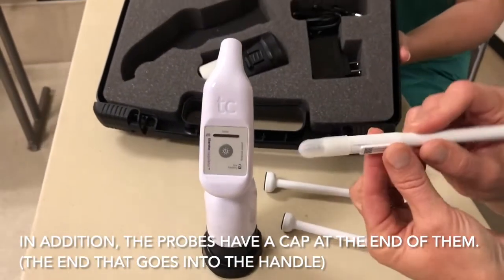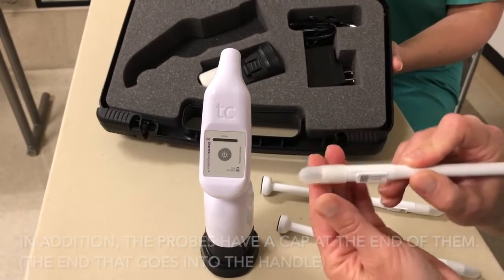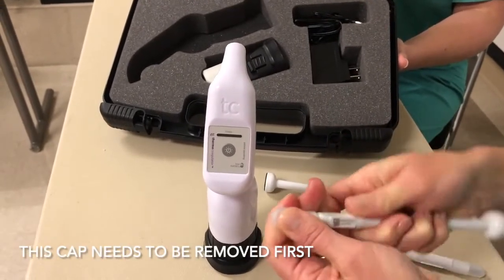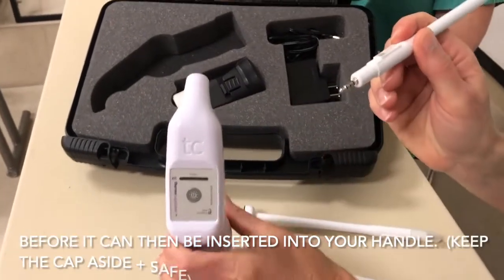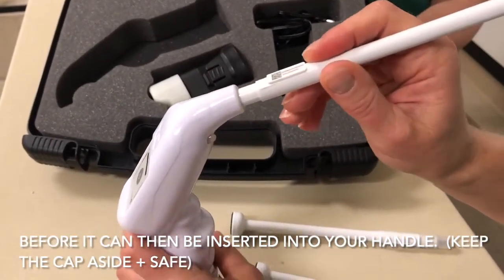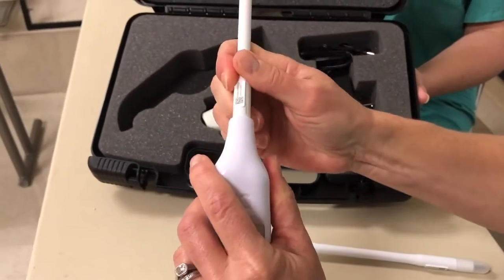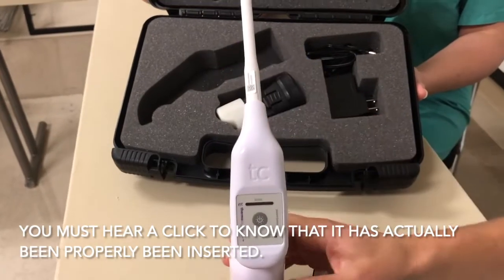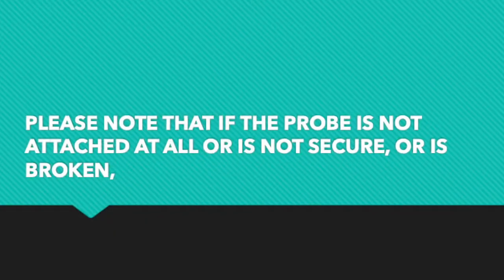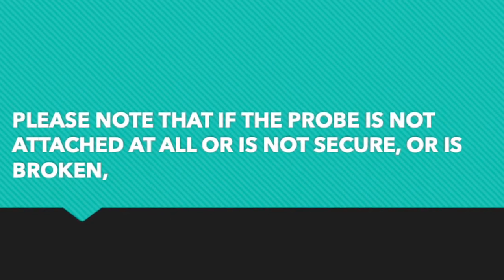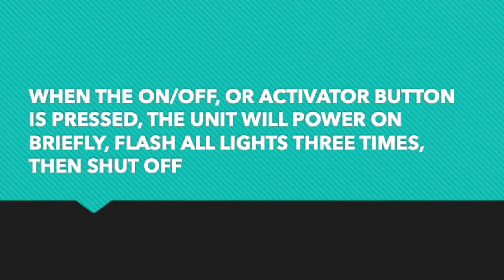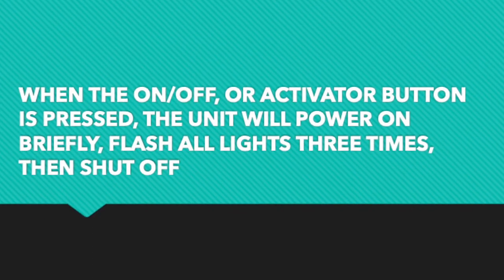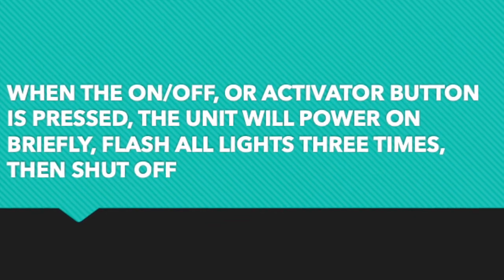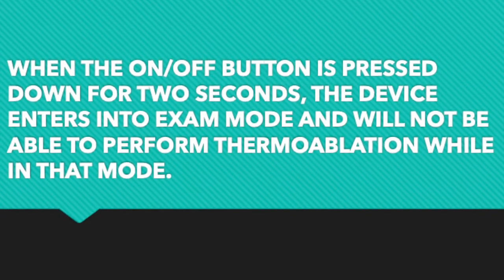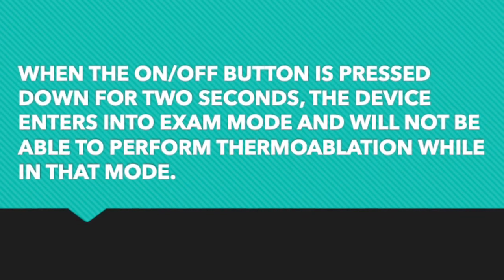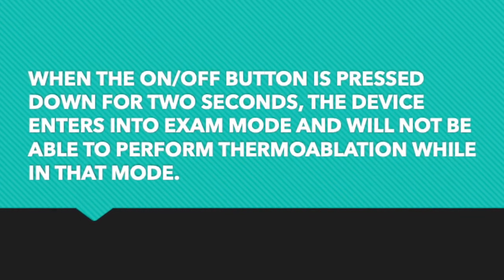In addition, the probes have a cap at the end of them. This cap needs to be removed first before it can then be inserted into your handle. You must hear a click to know that it's actually properly inserted. Please note that if the probe is not attached at all, or is not secure, or is broken, when the on-off or activator button is pressed, the unit will power on briefly, flash all lights 3 times, then shut off. Another tip is that when the on-off button is pressed down for 2 seconds, the device enters into exam mode and will not be able to perform thermoablation while in that mode.